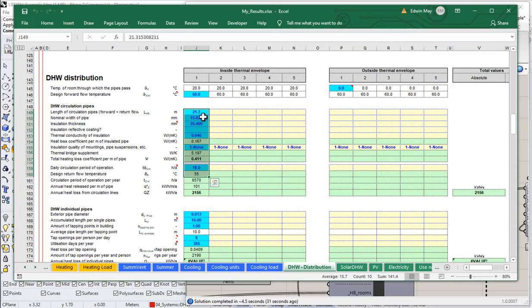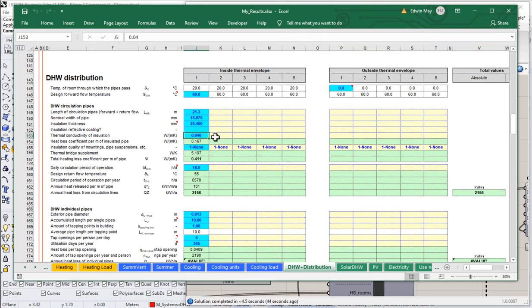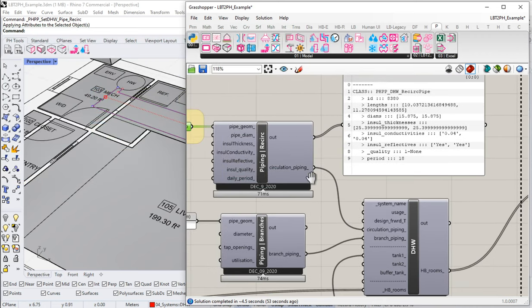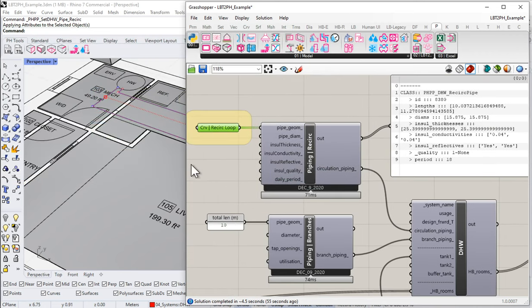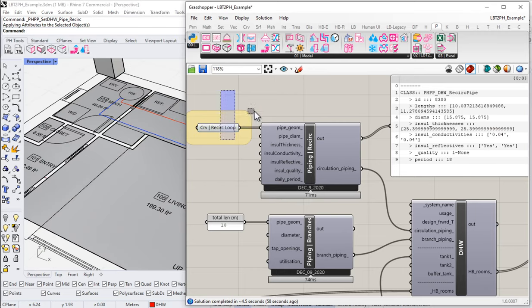There's our 21.3 meters total length, 15 millimeters pipe width, 25 millimeters of insulation thickness — so five-eighths of an inch and one inch — insulation conductivity like fiberglass, and a daily circulation period of 18 hours. You can change that — we can set it here in the daily period if we like.